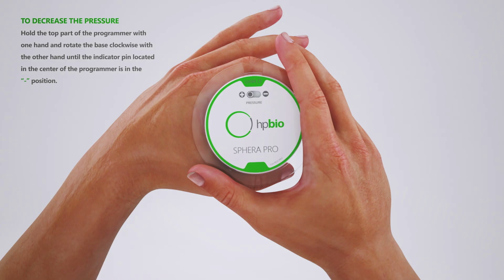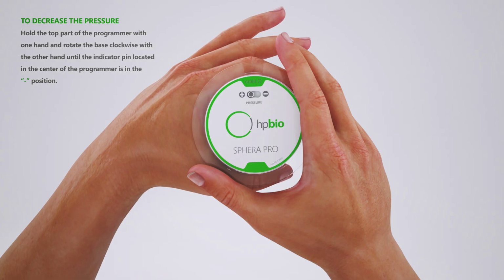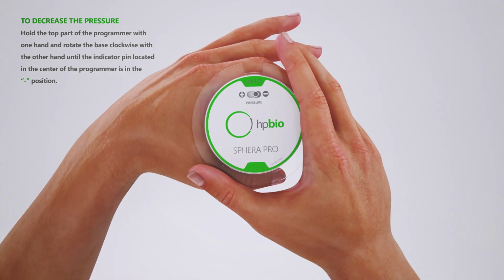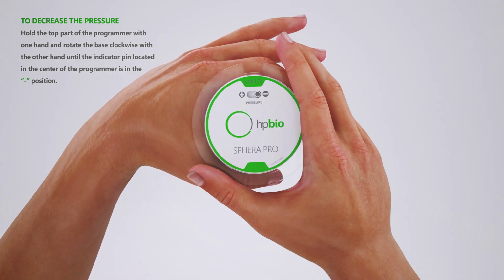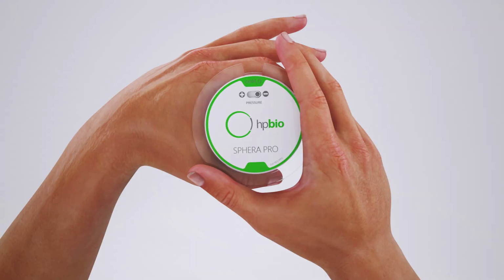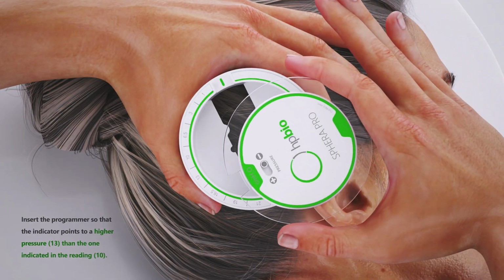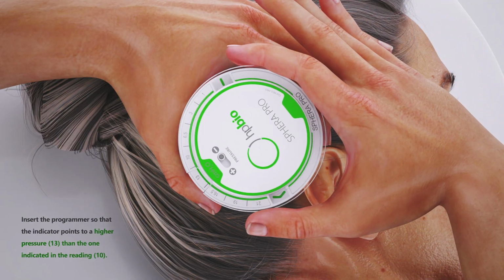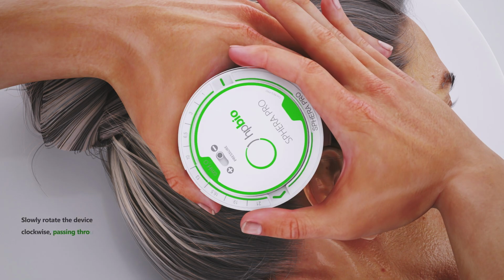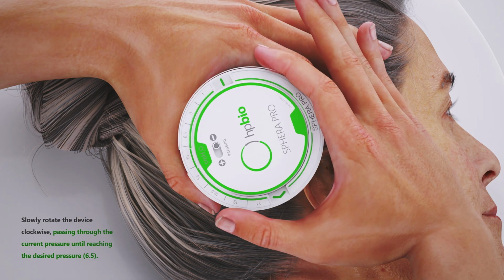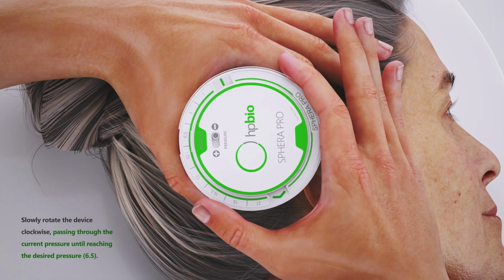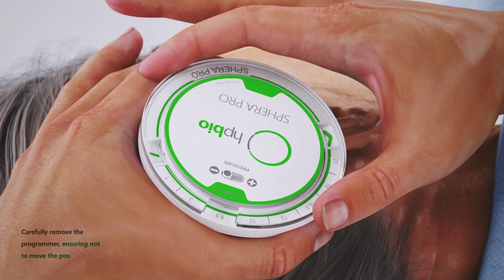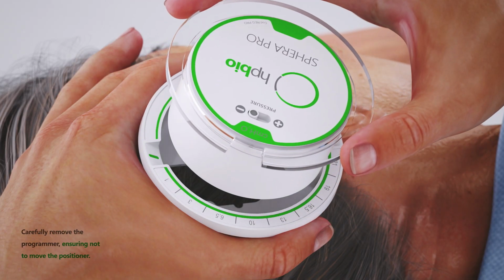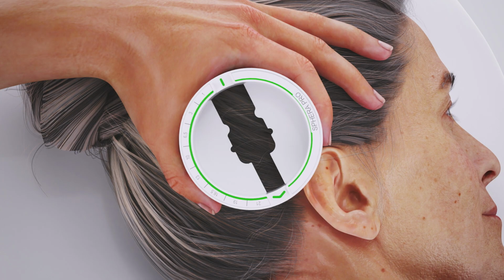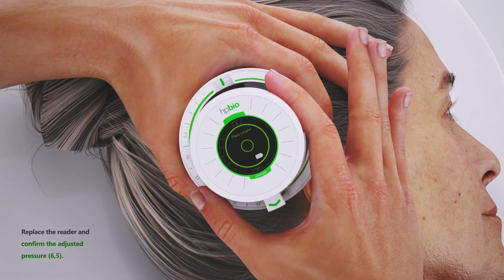To decrease the pressure, hold the top part of the programmer with one hand, and with the other, turn the base clockwise until the indicator pin located in the center of the programmer is in the minus position. Insert the programmer so that the marker points to a higher pressure than the indicated reading. Slowly rotate the device clockwise, passing through the current pressure until the desired pressure is reached. Carefully remove the programmer, ensuring not to move the positioner. Place the reader again to confirm the new adjusted pressure.